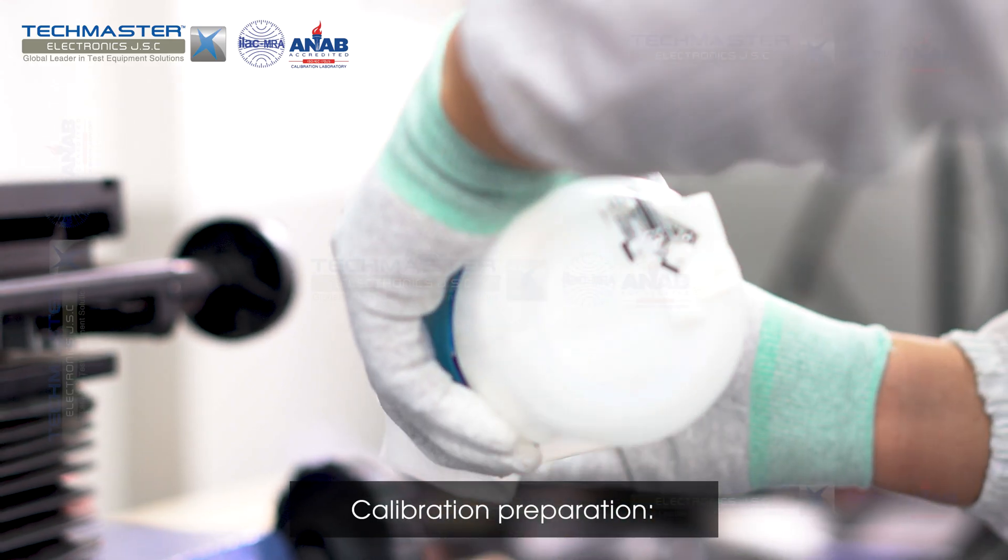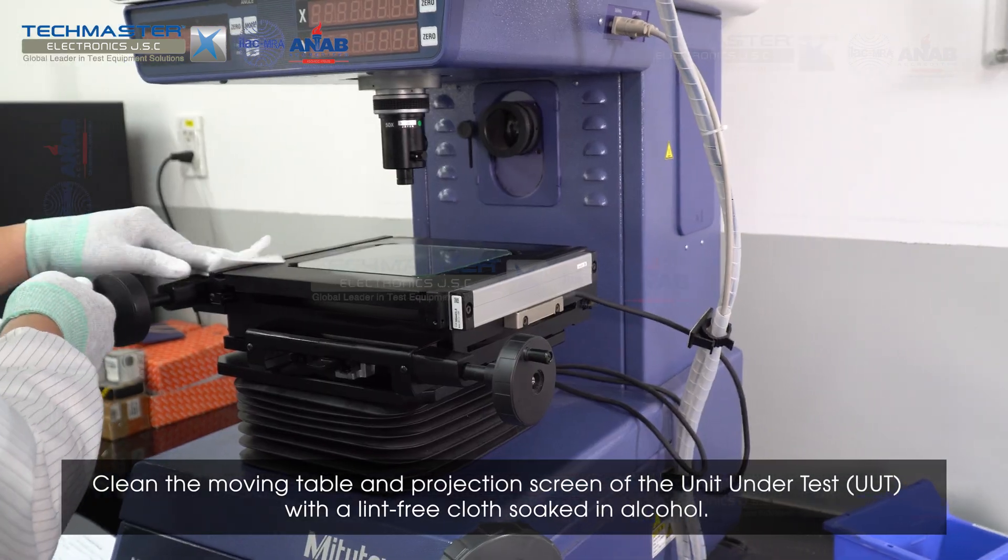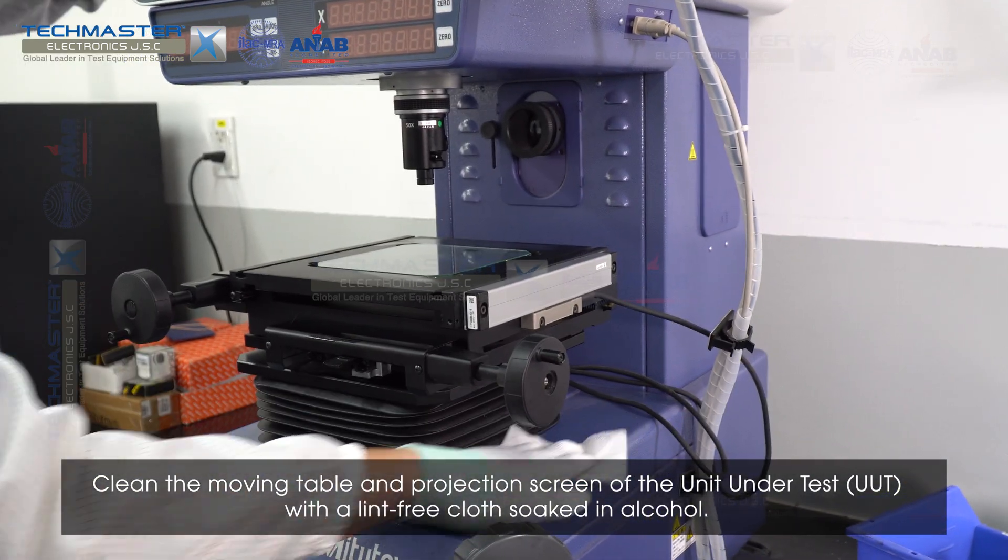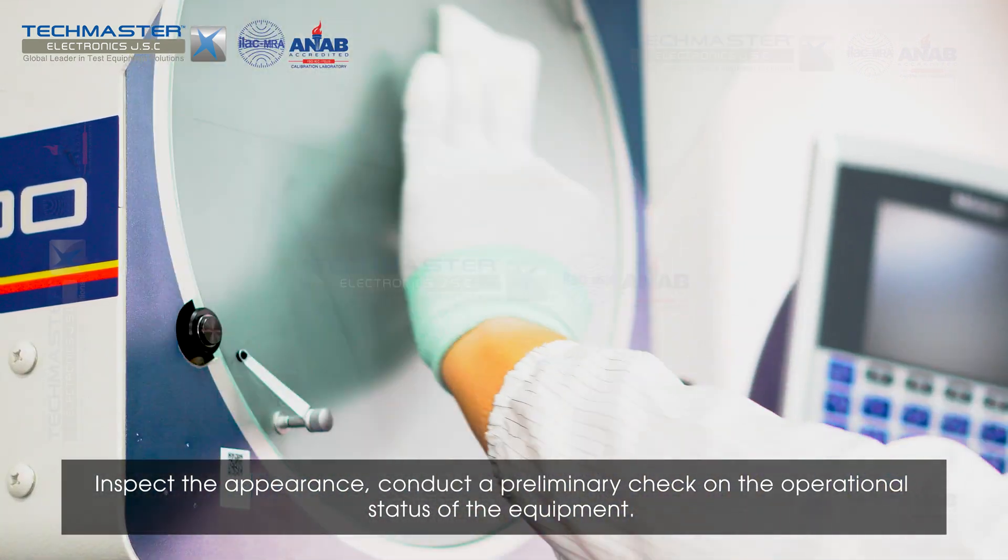Calibration Preparation: Clean the moving table and projection screen of the unit under test with a lint-free cloth soaked in alcohol. Inspect the appearance and conduct a preliminary check on the operational status of the equipment.